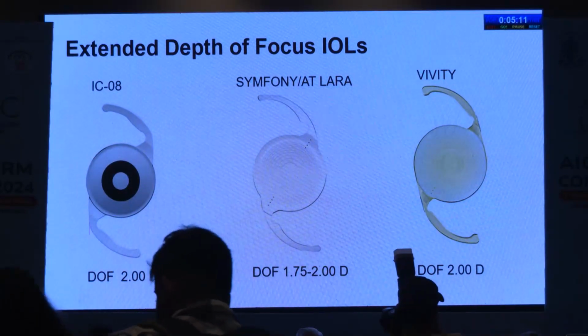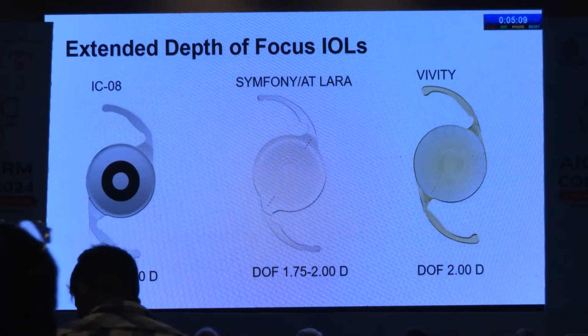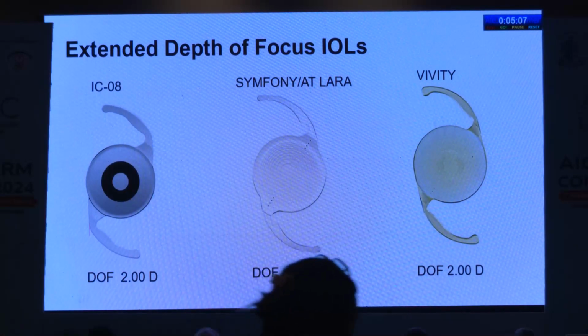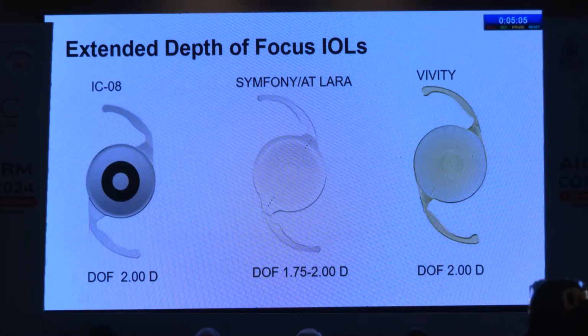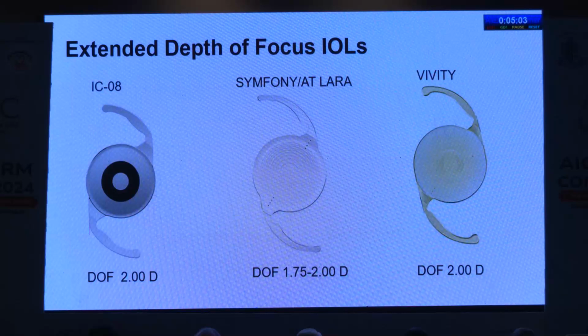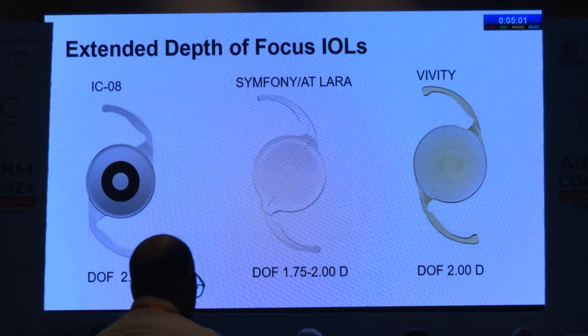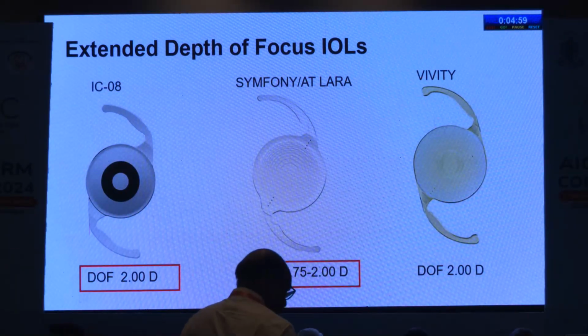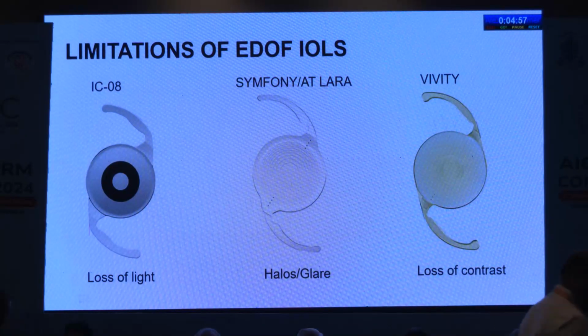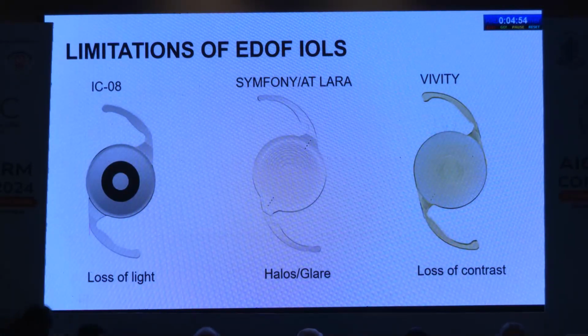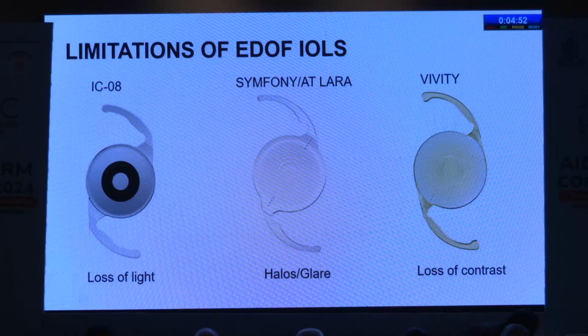So the extended depth of focus, the pure EDOF IOLs, like the IC8, has a depth of focus of around 2 diopters. The Symfony or the AT Lara has around 1.75 to 2 diopters, and the Vivity has 2 diopters. But what are the limitations of EDOF IOLs? There can be loss of light, there can be halos, glares due to the rings, and there can be loss of contrast.